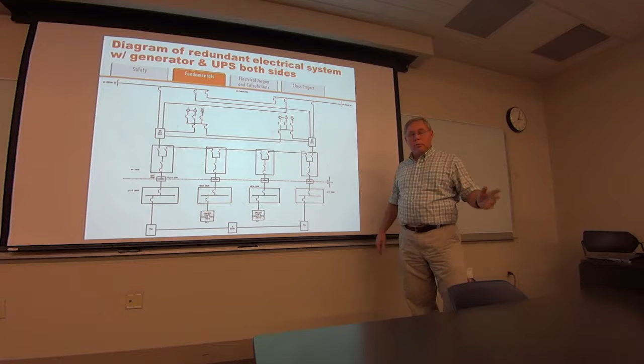When you get these UPSs down here at 600 volts, you get about 1,000 kVA per UPS, so you have to parallel them. The most you can usually get is about 4 MVA. Then you got to parallel 4 of those to get 16. And you got to have a building for them, so it gets really expensive.